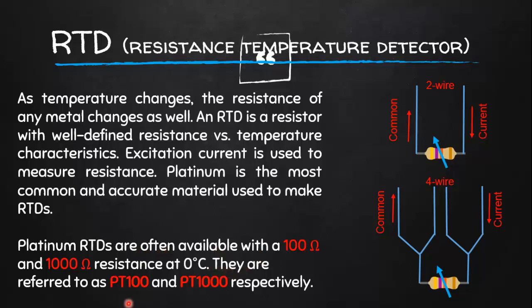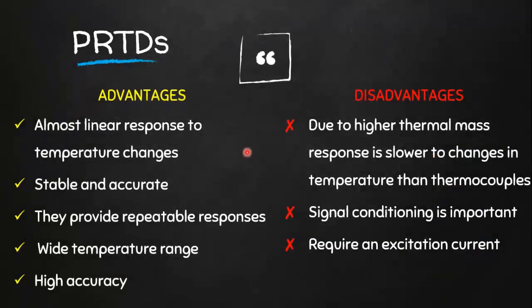Here you can see a two-wire PT100 RTD, and similarly we have a four-wire PT100. The four-wire configuration is more accurate than the two-wire. All RTDs require excitation current to measure resistance. The advantages of PRTDs include behavior that is almost linear with respect to temperature changes, and they are very stable and accurate, providing very good repeatable responses.